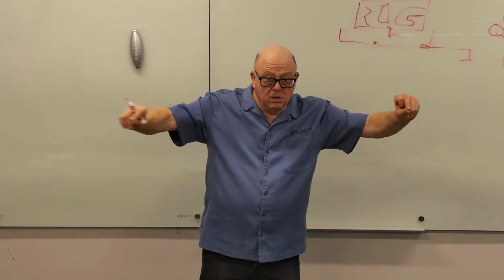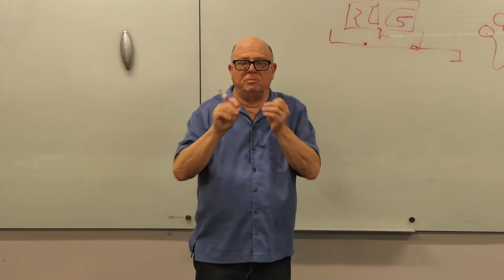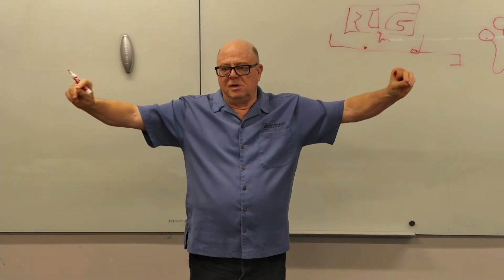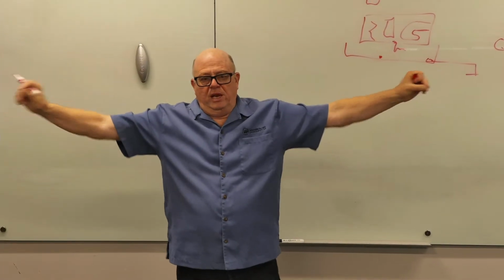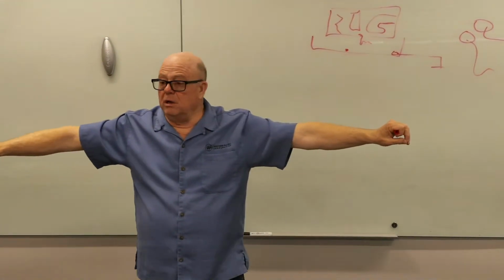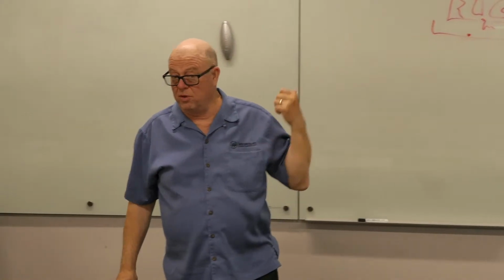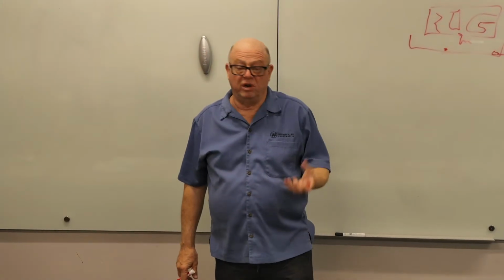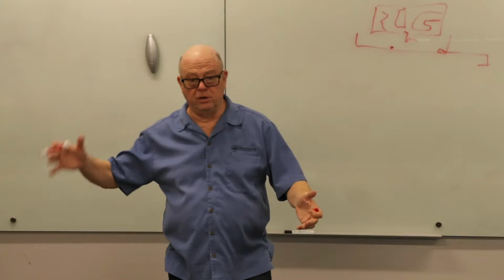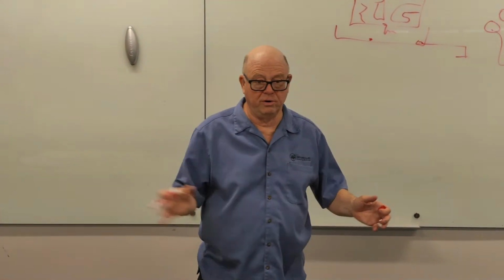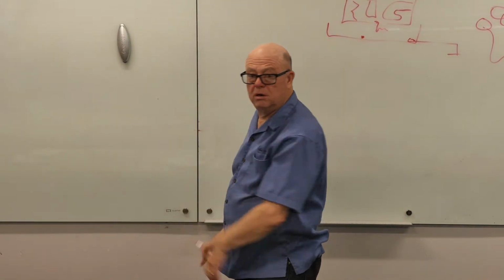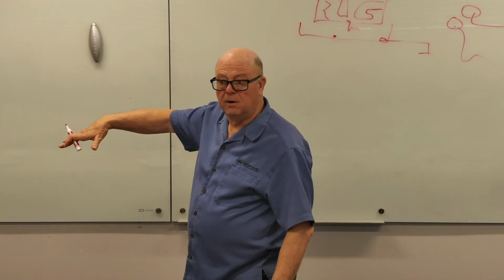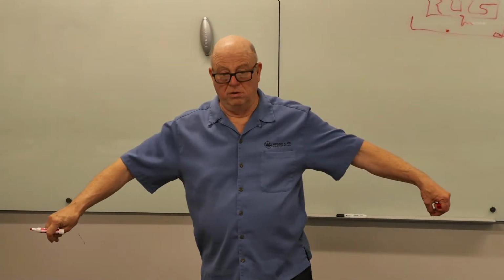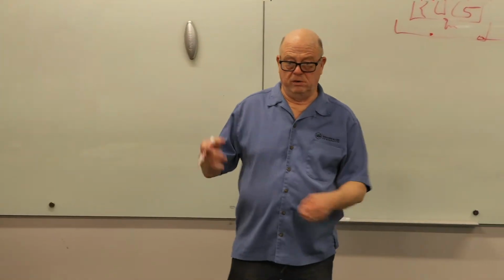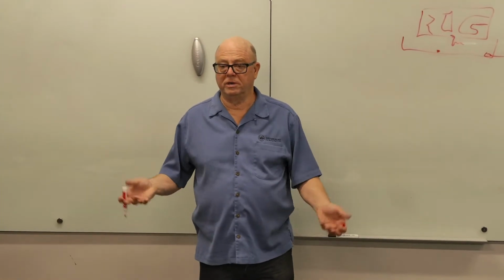The cable is just like the button, except it's got a jillion little buttons within the cable. And it lets you cover a much broader area. Costs a lot more than the button. But for example, if you've got a CRAC unit, computer room air conditioner, CRAC. If you've got a CRAC unit on a raised floor system, there will be a cable under that thing because you don't want the water getting down into your cabling.